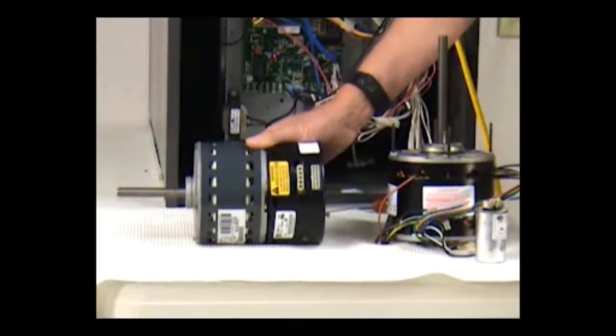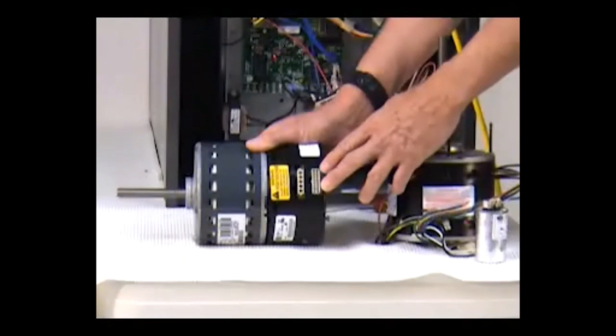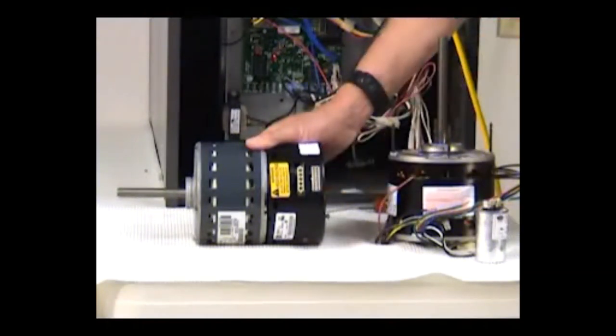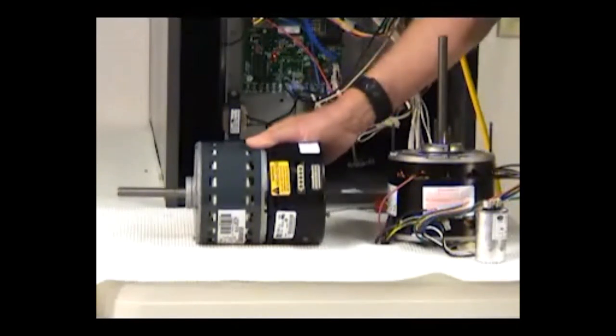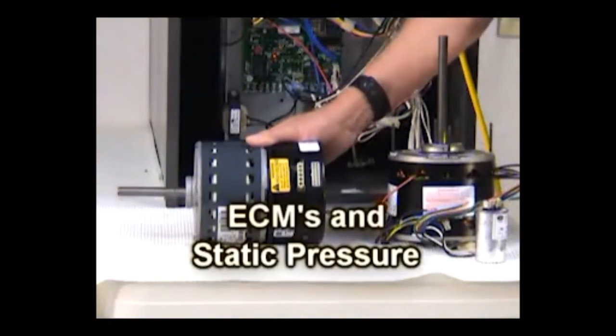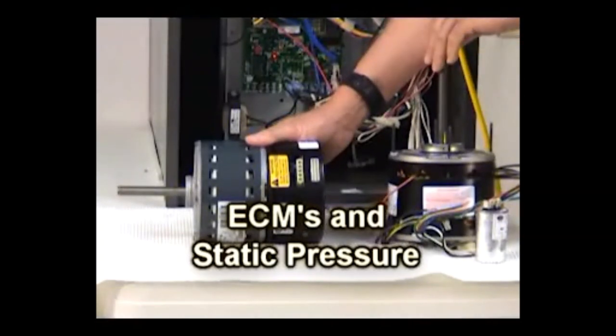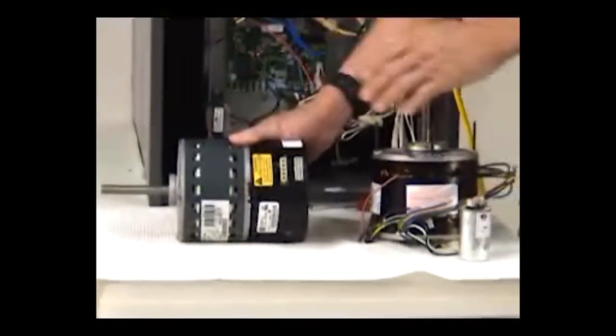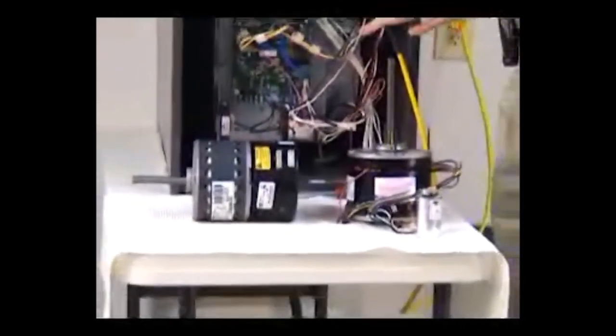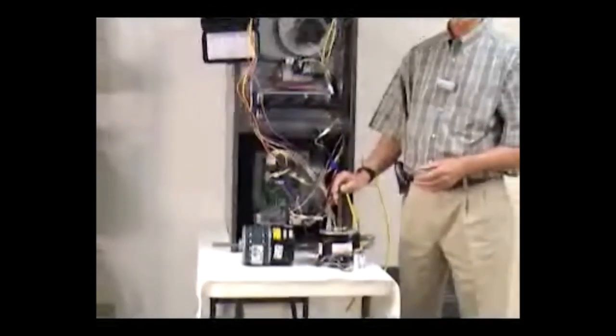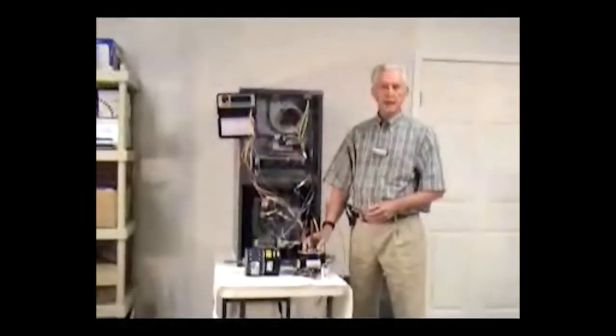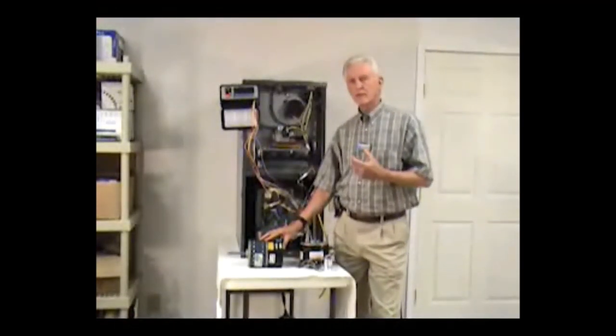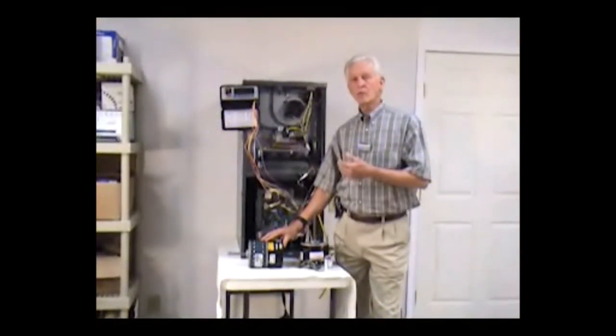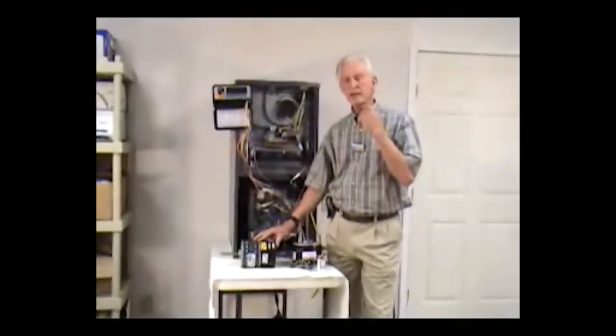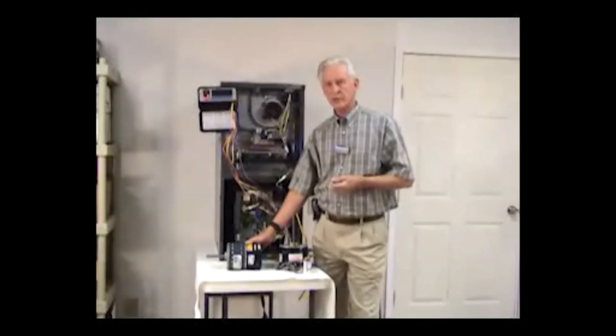So for our purposes today, what we will talk about is the 16-pin application that goes here that's thermostatically operated through the board that is on the air handler itself. To go back now and explain what's happening with this motor once we tell it what to do, where it has a super advantage, or a much bigger advantage if you will, over a split capacitor motor, is that we can go in a static range that will vary from actually zero all the way up to almost a full inch, and in some cases with some manufacturers, a full inch of external static pressure.